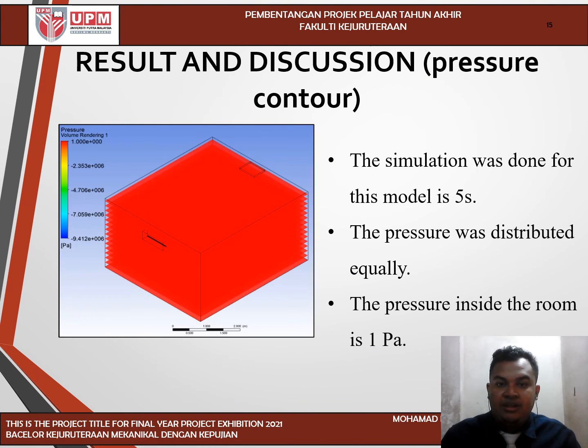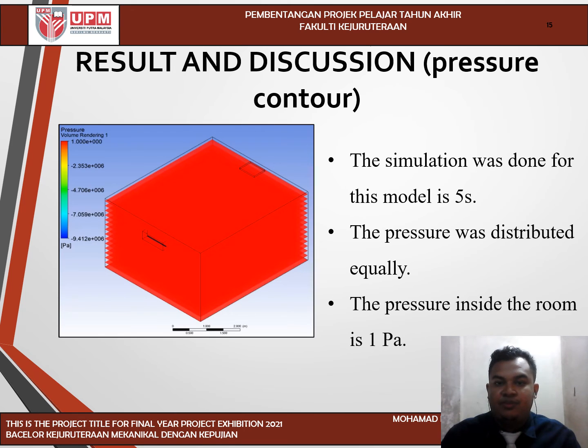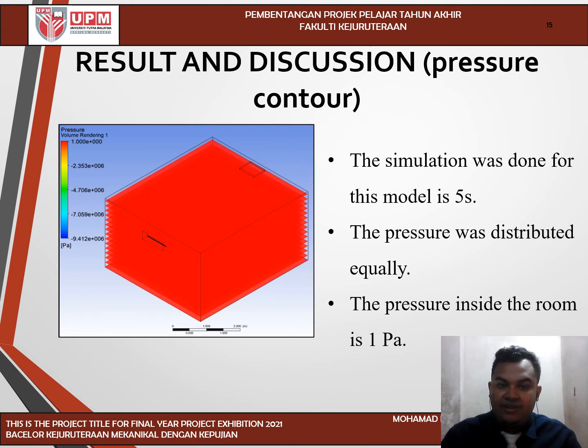For the results and discussion, the simulation time period is 5 seconds. The result of the pressure simulation in the room is 1 Pa. The pressure is distributed equally; however, the minimum criteria for an isolation room is 2.5 Pa.